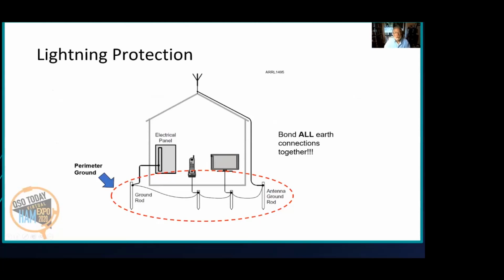Dirt. Okay, dirt is very resistive. It could be 10 or 25 or even higher ohms of resistance between these ground rods. So what happens if there's a big lightning pulse in the thousands of amps between 10 and 25 ohm connections? Well, you get 10 or 25,000 volts.